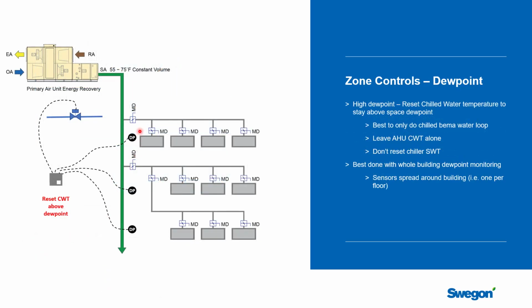Now, we were talking about using dew point sensors at each one of the control zones. That's just going to end up with a lot of dew point sensors. Another way to do it would be to have dew point sensors, let's say typically per floor. And remember what we were talking about earlier, it's actually really hard to keep humidity in one space.